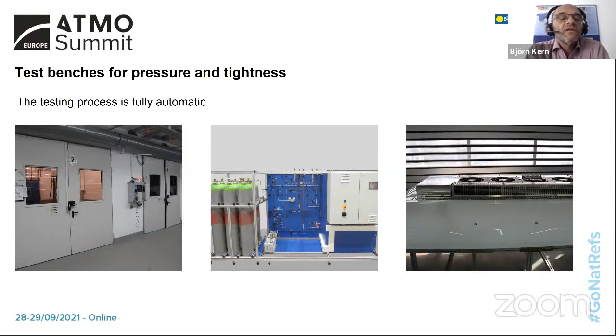It starts with high pressure, 160 bar, and has to stand under these conditions for 30 minutes. Then we decrease the pressure and do a leakage test. The test procedure for each unit takes around 1 hour, and after that hour we are sure everything is running well with no leakage, and the unit can go to the customer with a good feeling.